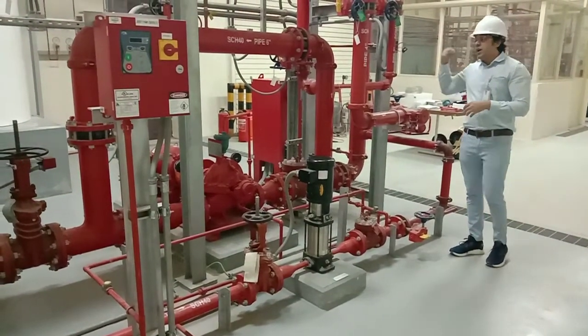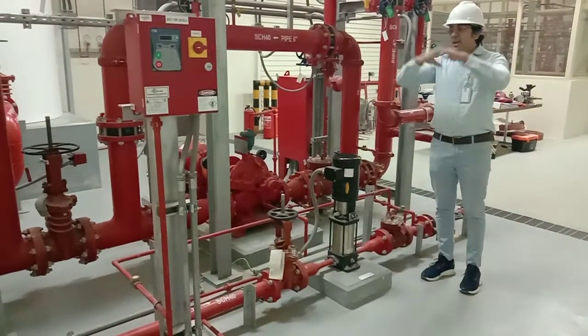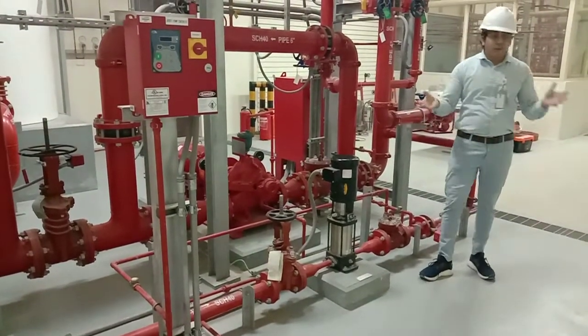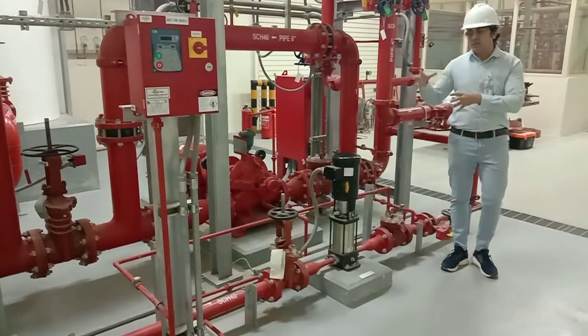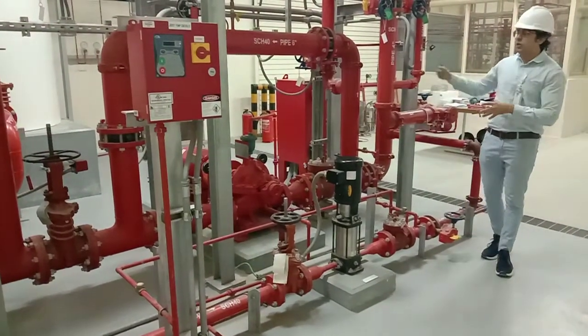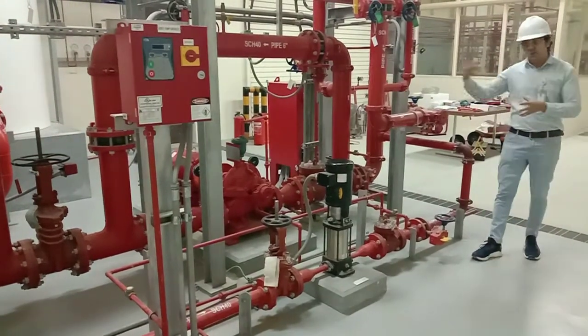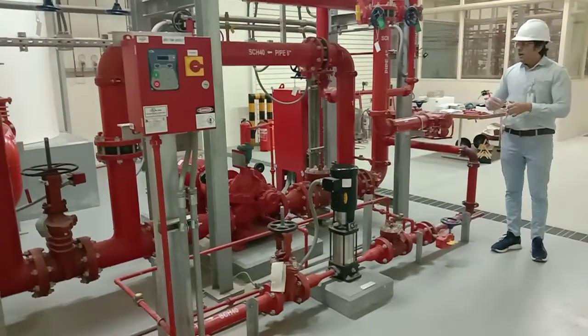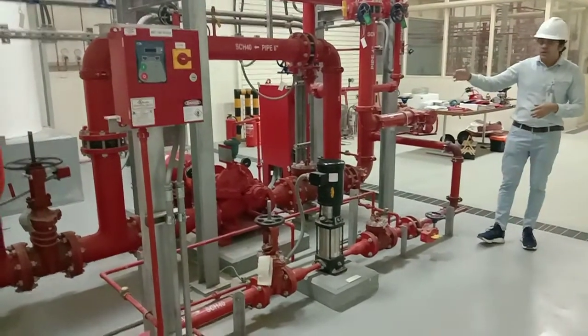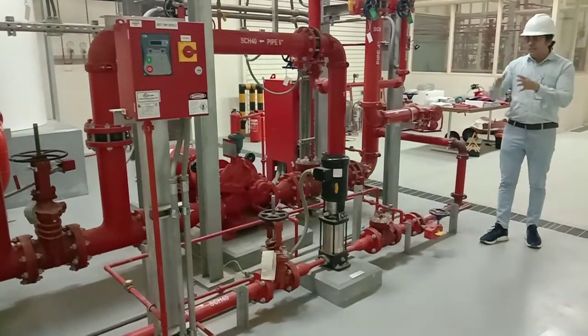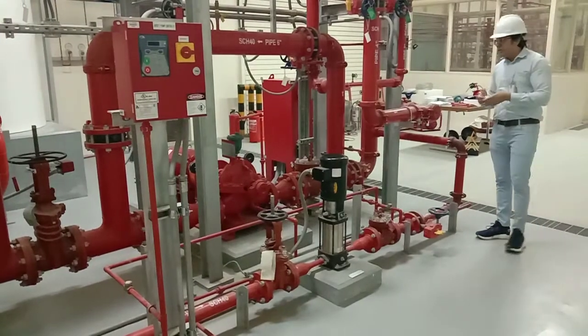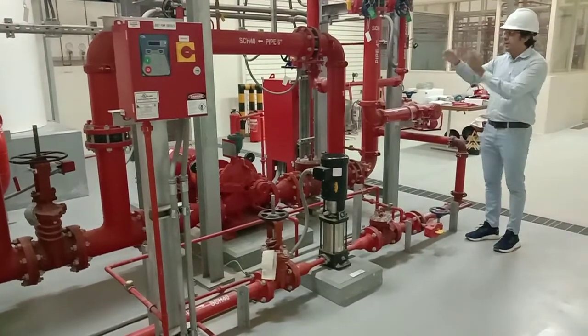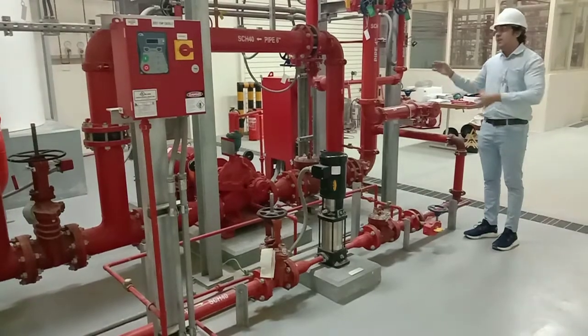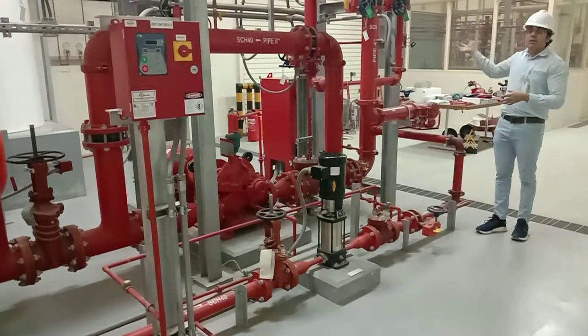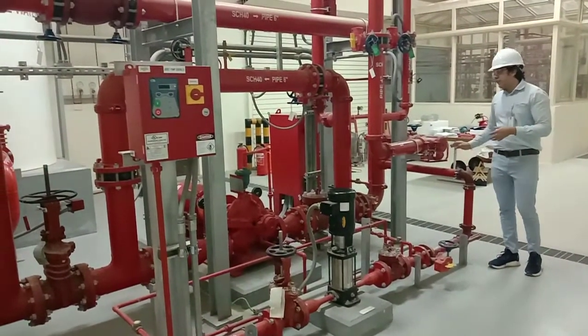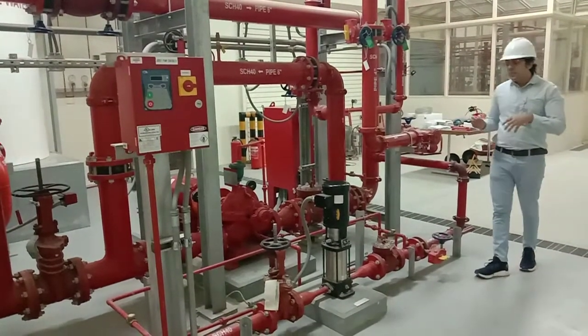Now, if the building is fully covered with fire and the electrical feeder connection to the motor is damaged and we are not getting power to the system, then comes the turn of the diesel pump. The first pump to start is the jockey, as the pressure goes below its setpoint, then the second, the electrical pump, will start. If even the electrical pump is not supplying the requirement, the diesel pump will start and boost the pressure in the system to fight the fire. This is all about the jockey pump.